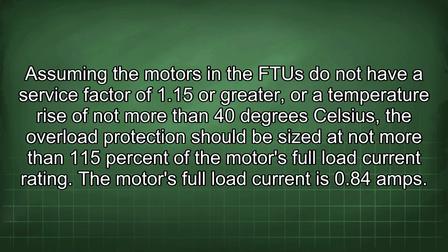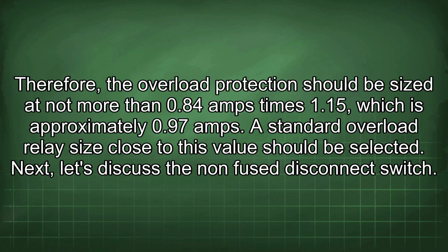Assuming the motors in the FTU do not have a service factor of 1.15 or greater, or a temperature rise of not more than 40 degrees Celsius, the overload protection should be sized at not more than 115% of the motor's full load current rating. The motor's full load current is 0.84 amps. Therefore, the overload protection should be sized at not more than 0.84 amps times 1.15, which is approximately 0.97 amps. A standard overload relay size close to this value should be selected.